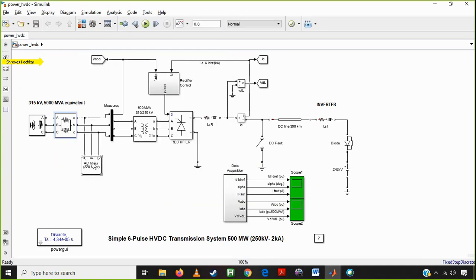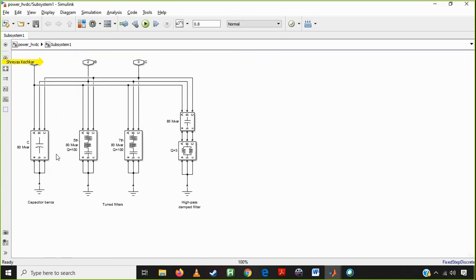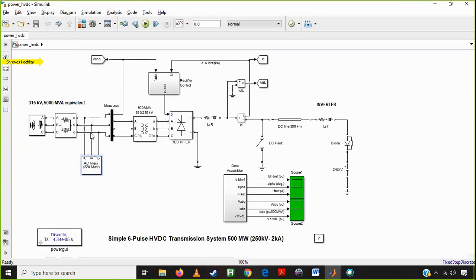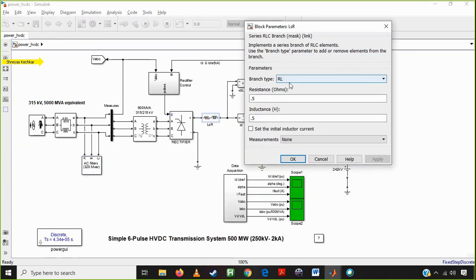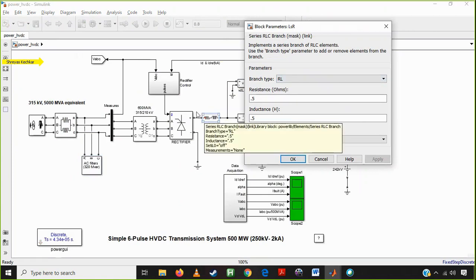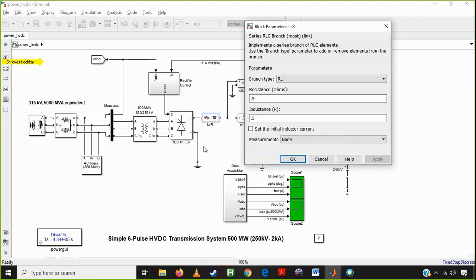When we are having a converter, we require a large amount of reactive power. So here we are using filters: there is a capacitor bank, tuned filters, high-pass filter, and a damping filter. After the converter, we also connect a smoothing reactor. The smoothing reactor reduces the pulsation in the DC system — the output of the rectifier has some kind of pulsation, and we use this inductor to smooth it out.